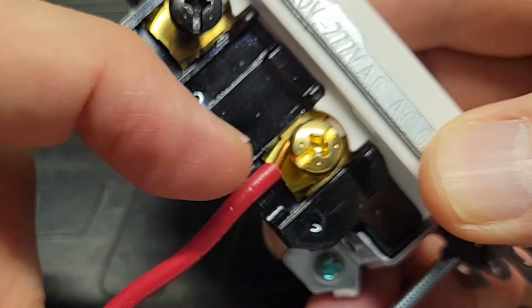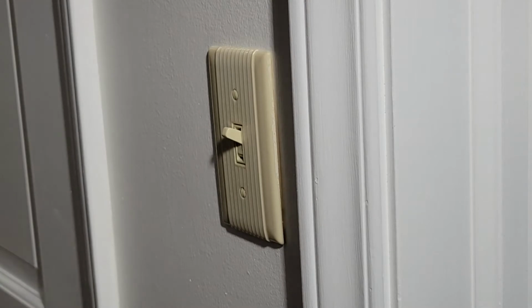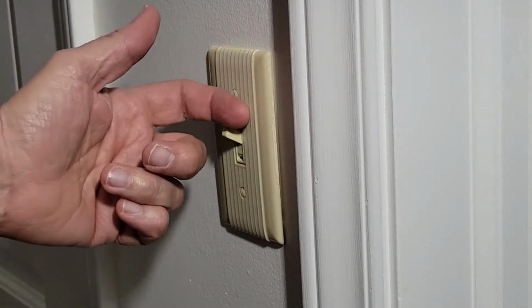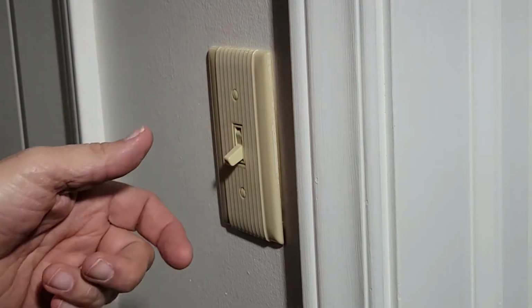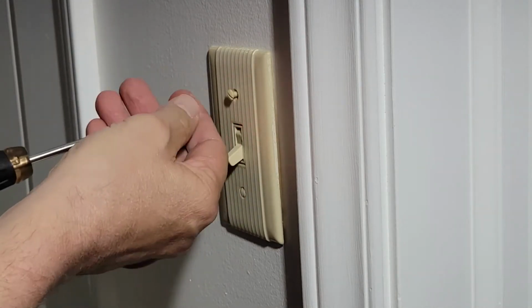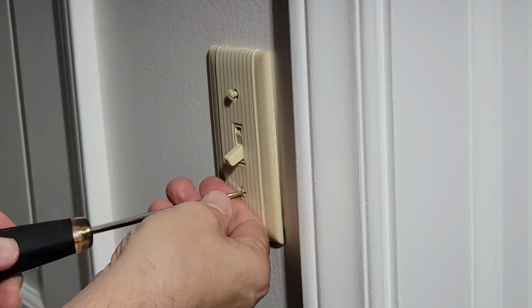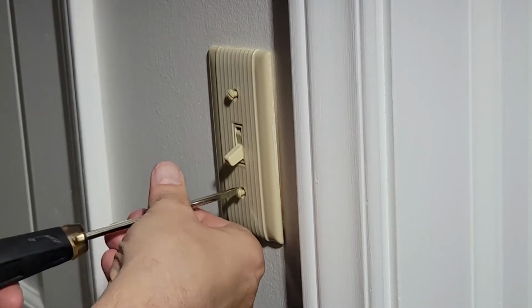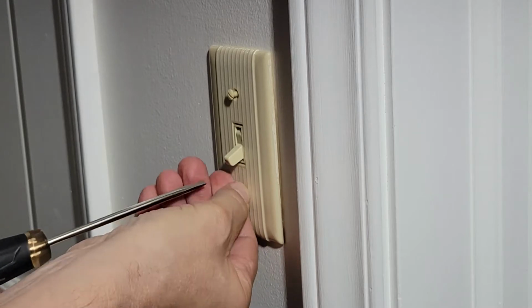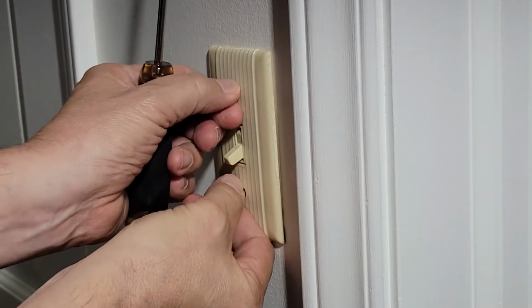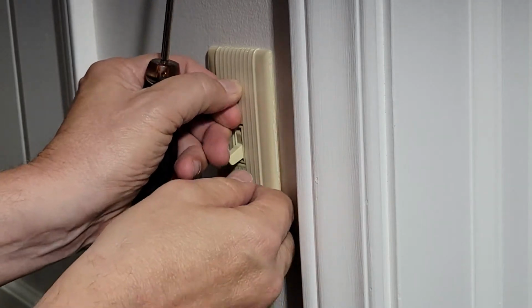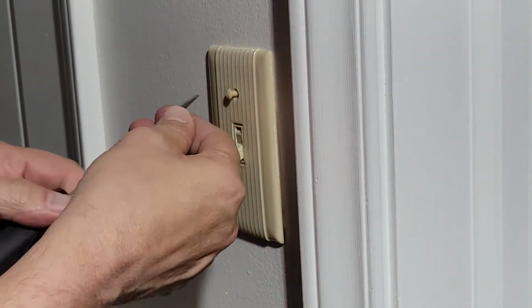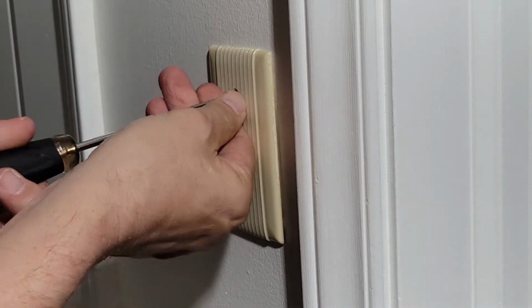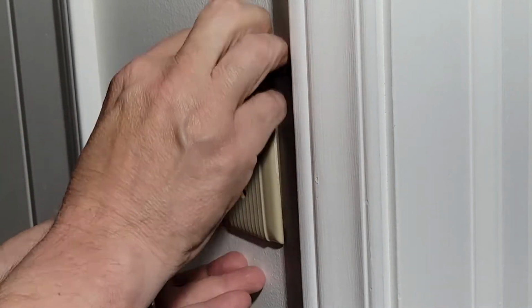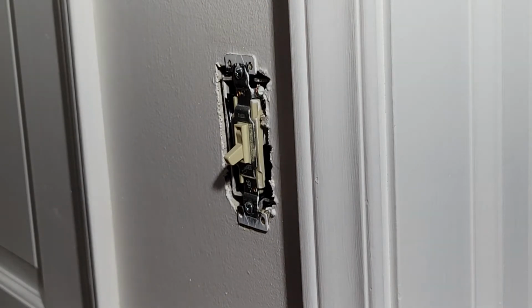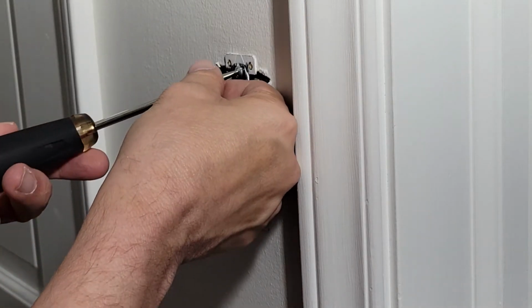The very first thing we do is turn off the circuit breaker so that there's no power at the switch. Once satisfied that there is probably no power at the switch, we remove the faceplate—I only say that because I still need to verify that the wiring inside is not hot, and until I confirm that for myself, I'm going to proceed with caution. We take the faceplate off and remove the switch.